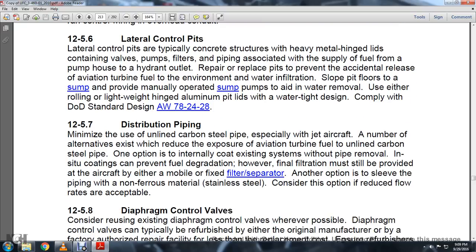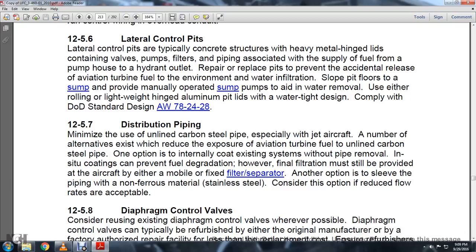Section 12-5-7: Distribution piping. Minimize the use of unlined carbon steel pipe, especially with jet aircraft fuel. Alternatives exist to reduce exposure of aviation turbine fuel to carbon steel pipe. One option is internal lining of the existing system without pipe removal. However, note that fuel-quality filter separation must be provided to the aircraft via mobile or fixed filter separators.